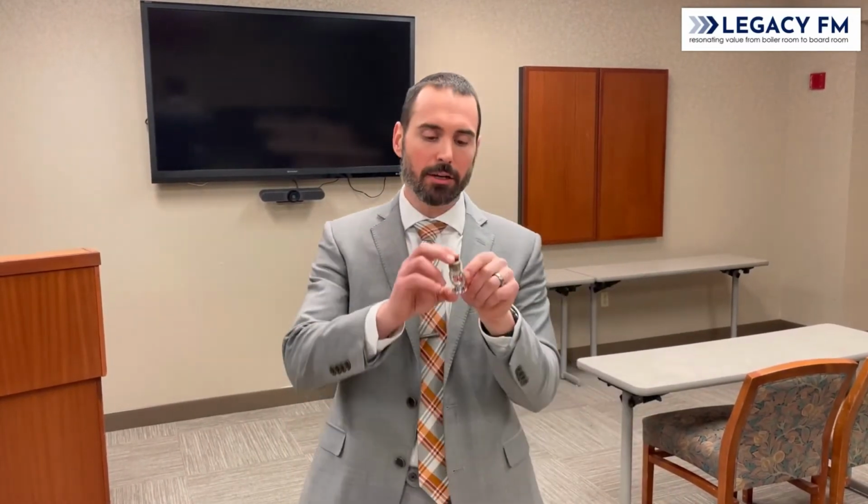The standard response, this one is just a standard response, I just know it. You can have a fusible link style quick response. They do make them, but this one is a standard response. Or we'll have a picture down below showing a standard response frangible bulb, which is a thicker diameter frangible bulb than this. And again, it's the performance characteristics of how they operate during a fire.